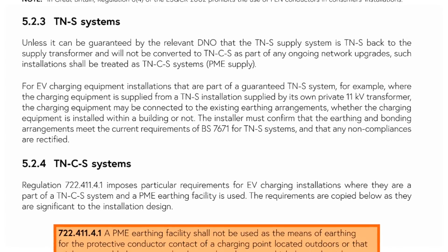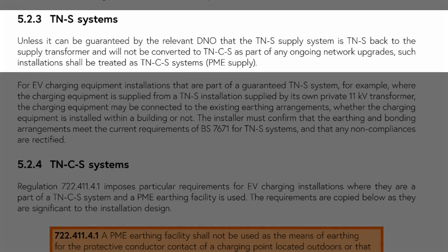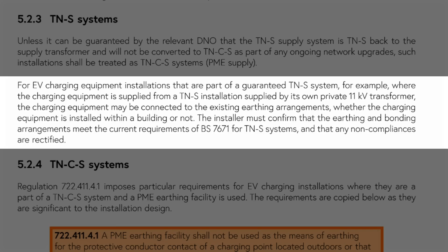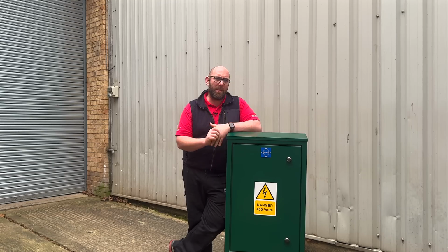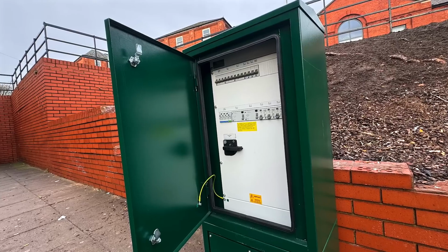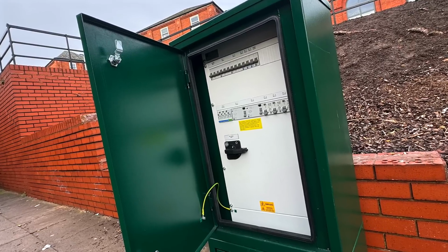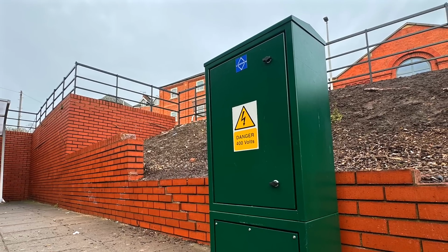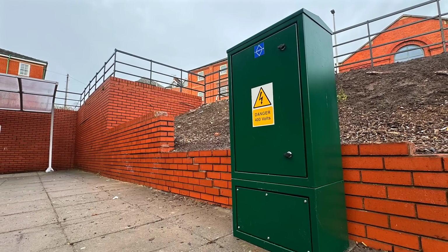This is why the code of practice states that unless we can guarantee that the supply is TNS and comes from its own transformer, we have to treat it as a TNCS, and this means ensuring we provide protection for broken PENs. Now, this normally takes the shape of open PEN protection, which is fitted as standard to most EV chargers. Things get more interesting as well when we look at feeder pillars like this one made by Lewden and the earthing arrangements required, and I'll be going into more detail in a later video.